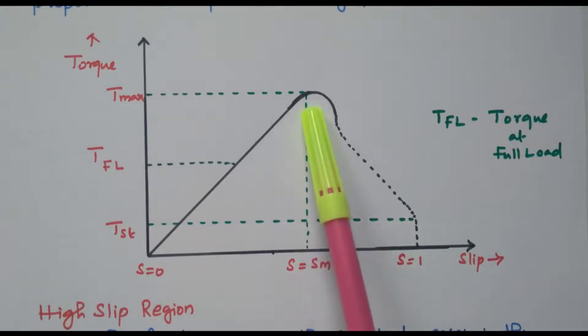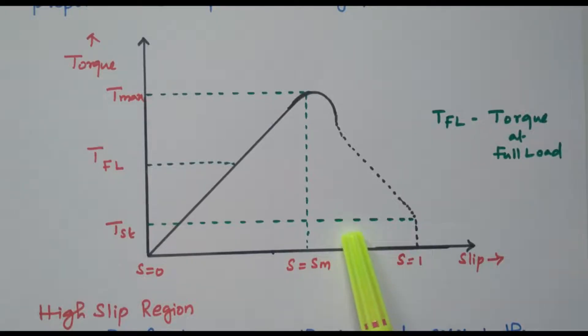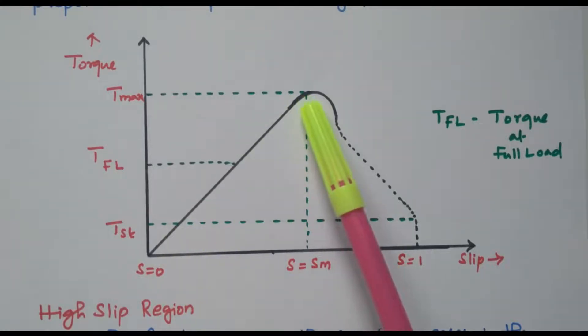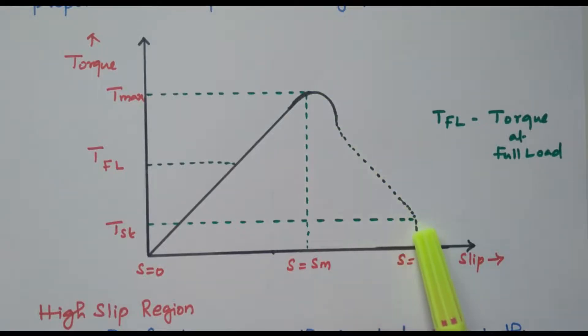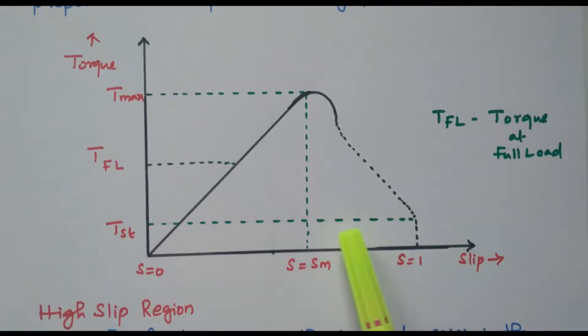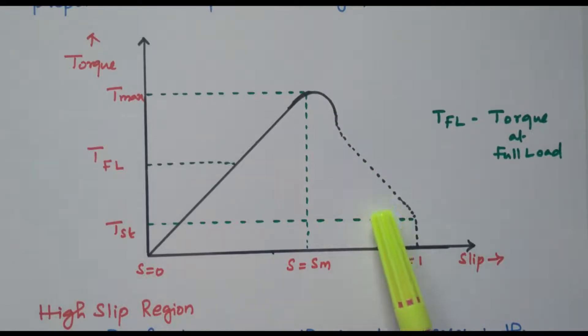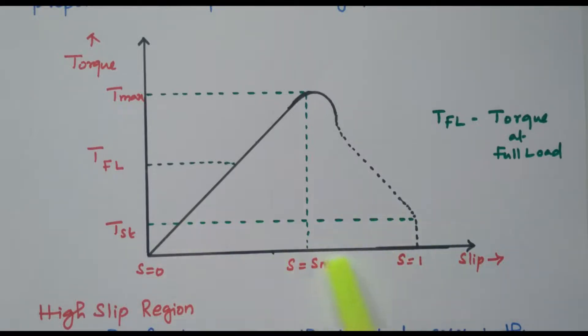Beyond the maximum torque, if you load the motor, the speed decreases slowly and reaches 0, and the motor will stop. We can load the motor only up to the maximum torque. Beyond maximum torque, if the motor is loaded, the torque decreases and becomes 0, so the motor will stop. This is the low slip region and high slip region of the entire torque slip characteristics.